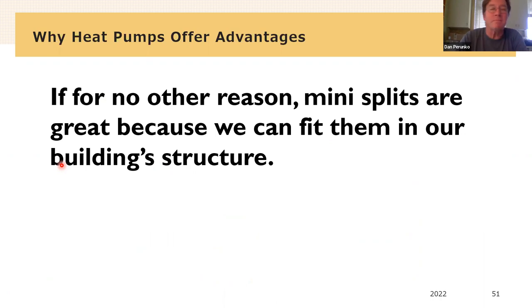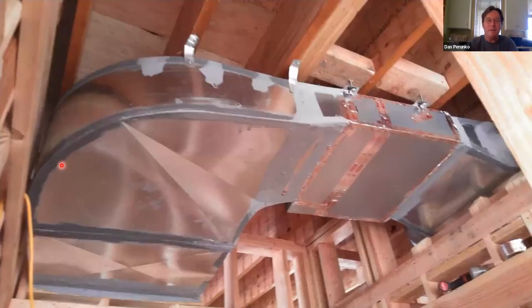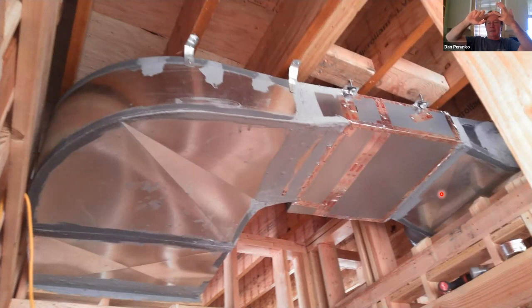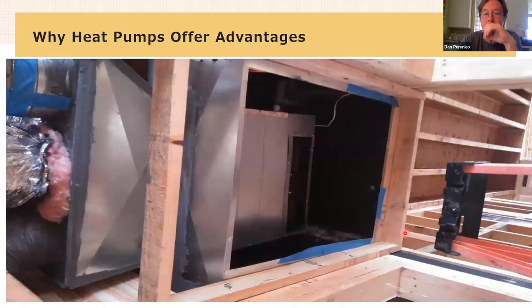So I said this earlier that the mini splits allow us to fit them into the building well. So this is a ducted mini split system. The return is to your left. The air handler is here and there's a supply plenum there. It's a new construction job, so this is a little easier to do, although we've done things like this in retrofit. There's just going to be drop ceiling in the closet, in a mechanical space, and over a little hallway. This entire duct system exists in this drop ceiling, and it conditions this hallway that's out here, a bedroom there, sort of a closet and dressing area, shower, and water closet, right? So it's just doing this little suite. This is a super compact system. I don't love these because of noise potentially.